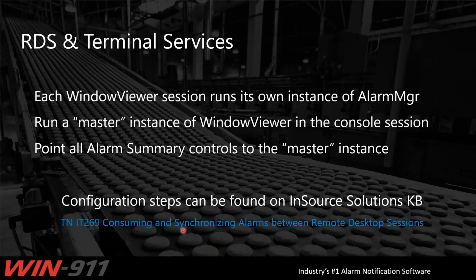So one thing that can happen is you have your InTouch server, you open up WindowViewer, and it spawns an AlarmMgr in session 1. But if someone were to log into that with RDP and open up another session of WindowViewer, it'll spawn a second AlarmMgr in session 2. If a third person logged in through RDP, you would get a session 3 and so on. And this can make Win911 confused on which one to attach to. So typically you want to create a master instance so everything runs in session 1.